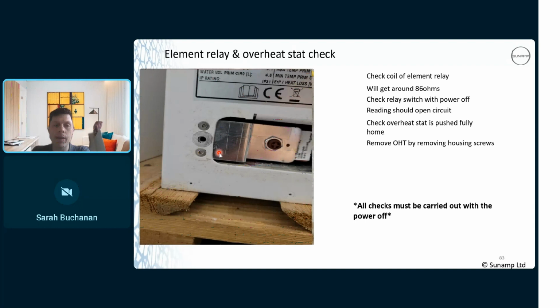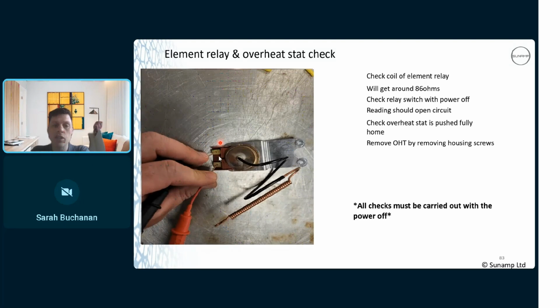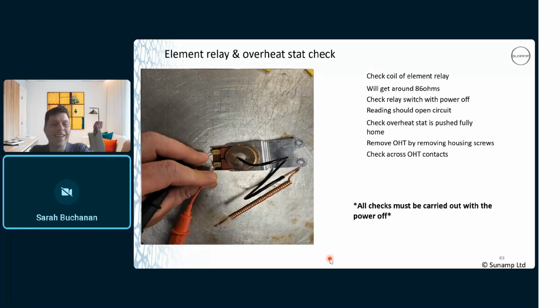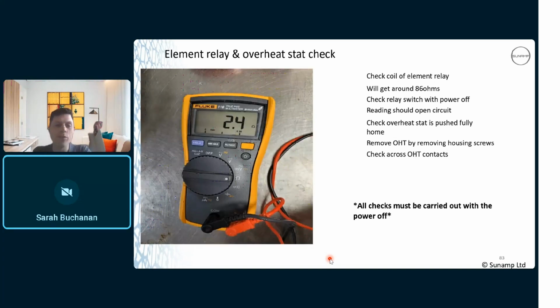You can check it by removing these two screws and just checking across the contacts there. Can anybody tell me what you should be getting across the contacts? Would it be an overheat stat wired in series to the element? Any takers, Sarah? No one's fast enough. Do you want to have a crack at it? Someone said closed. Yeah, exactly. You're looking for continuity through it, across it.